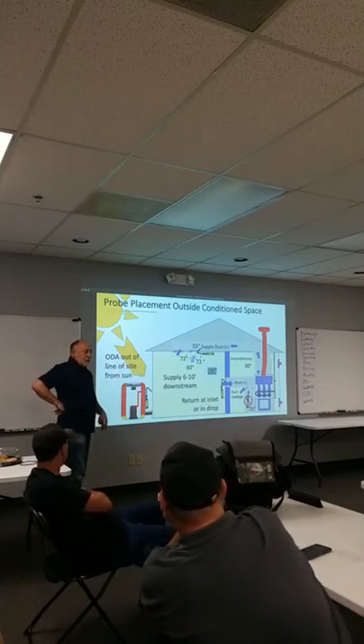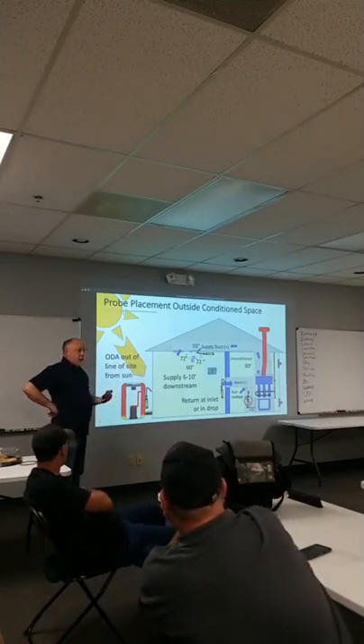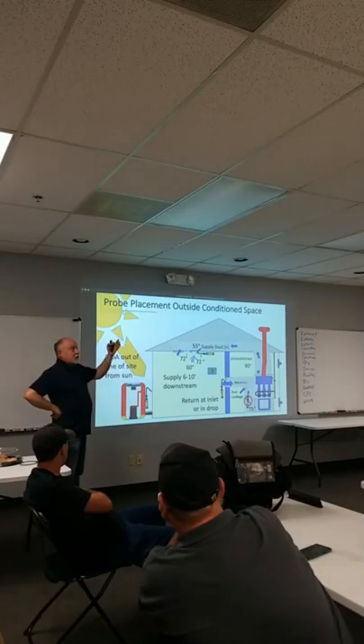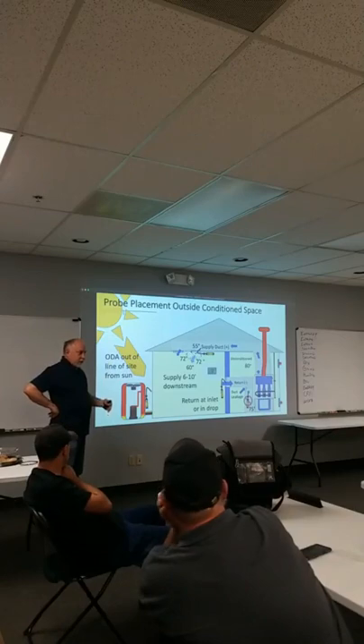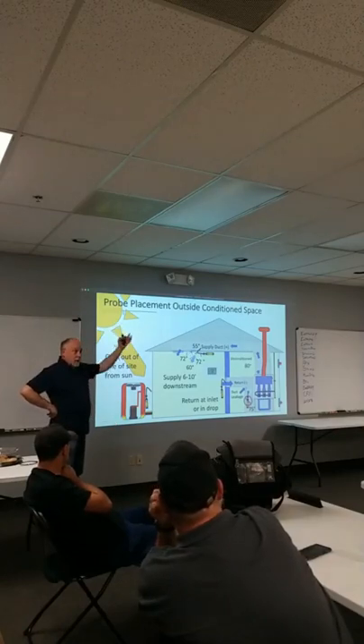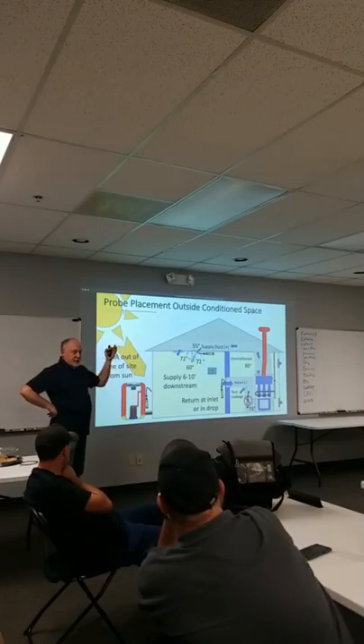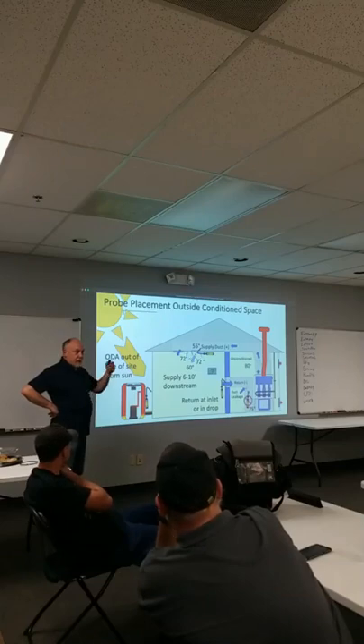A lot of technicians make a mistake, especially when you're younger, in that you explain away everything that you see, right? You go, well, it returns up to the ceiling, and obviously hot air rises, so it must be hotter at the ceiling than it is at the floor. In reality, in a well-conditioned room, there may only be 1 to 2 degrees difference between the floor and ceiling. Are we talking about cooling mode or heating mode? Yeah. Well, in heating mode, you could definitely stack some heat at the ceiling, but on cooling, it's gonna be pretty evenly dispersed throughout the space.